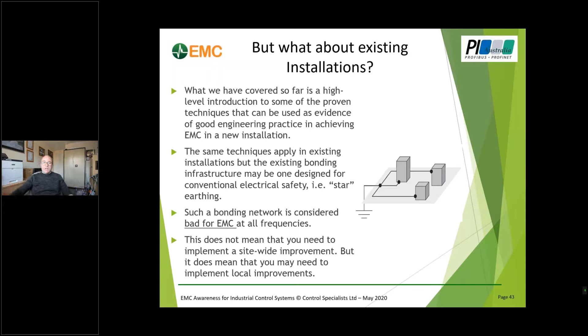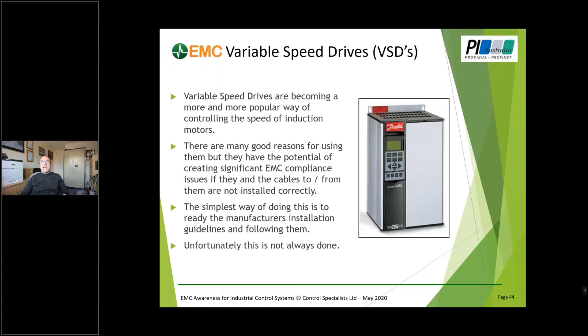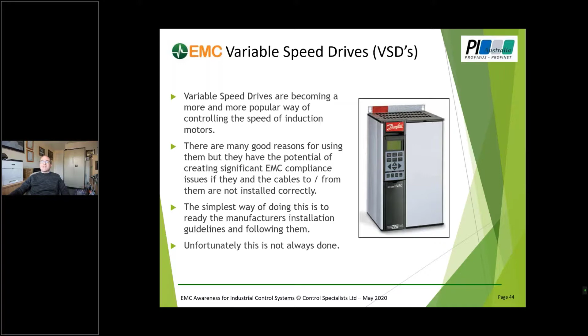Variable speed drives then - they're becoming more and more popular as a way of controlling the speed of induction motors, and there are numerous benefits in doing this. The simplest way to achieve compliance is to follow the manufacturer's guidelines. The problem is it's not always done, and when that's the case, it can be quite expensive to go back retrospectively. So what is the problem then?